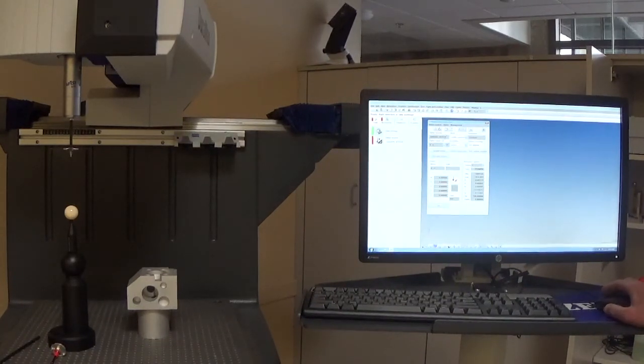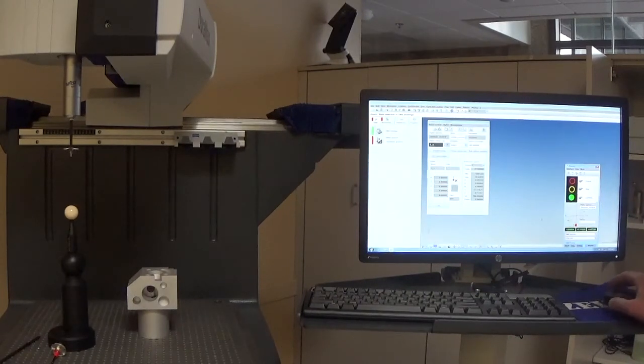So now I've built my stylus system. I'm going to click on the stylus name drop down, select the 1Z. I can go to my stoplight and see that I've got number 1 selected. It has a red X, so it's not qualified. So I need to qualify that. So I click on the Qualify Stylus button. It goes through some confirmation windows. I click OK, and now I can probe that sphere with stylus 1, and it will do the qualification of that.